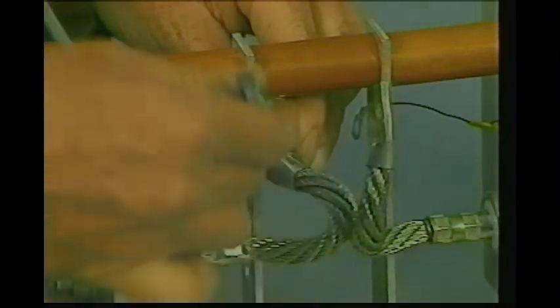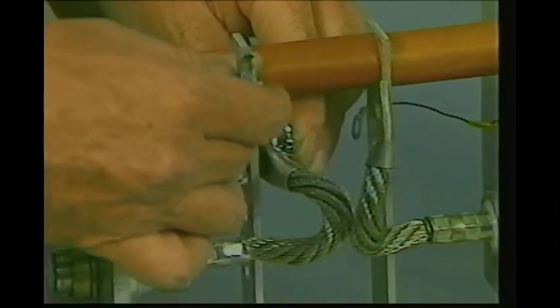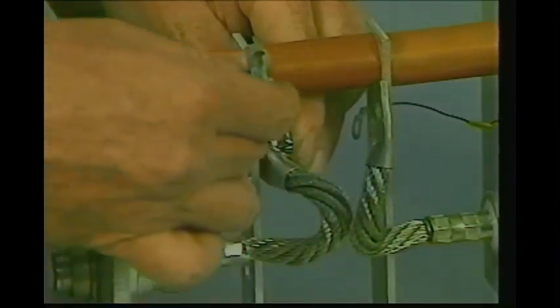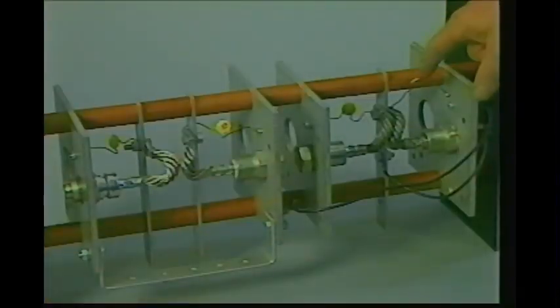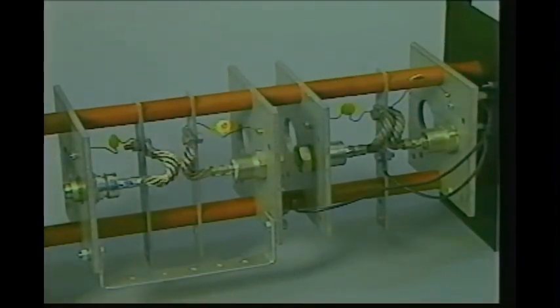At this point, reattach the pigtails of each of the three remaining diodes. While making this repair, also inspect the physical condition of the capacitor across each diode, along with the suppressor. If there is evidence of the capacitor or suppressor being burned or broken, it should be replaced at this time.